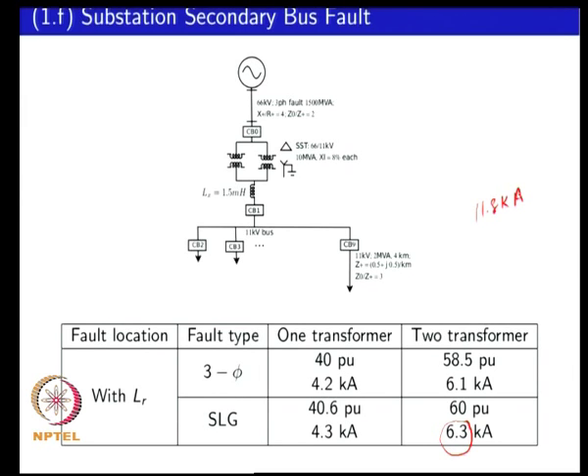By adding a reactor you could reduce the fault rating required for a large number of breakers. Potentially, the cost savings in circuit breakers 2 through 9 might be greater than the cost of the reactor being added. Of course, you will have to look at the voltage regulation introduced by adding that 1.5 milli-henry reactor, as well as the cost of the inductor and the losses introduced — but if it works out to be economical, you could add impedances to ensure your fault current level does not become excessive.